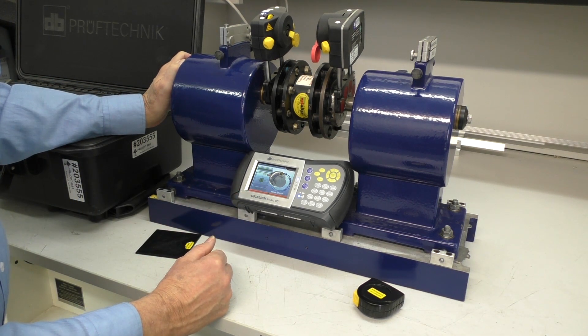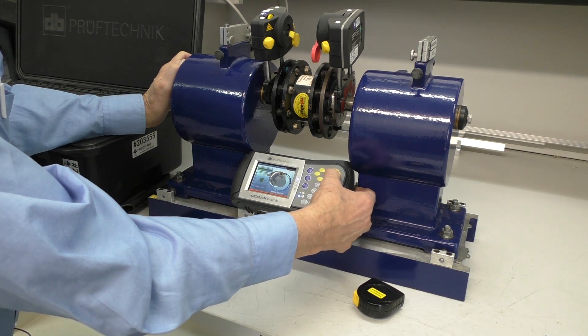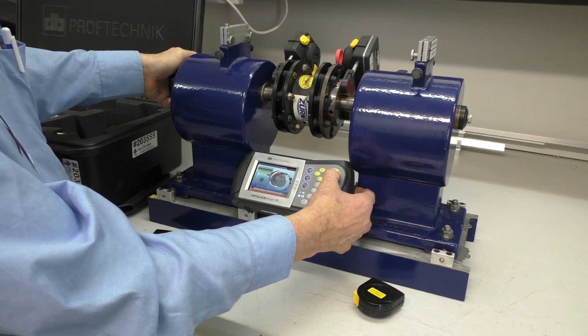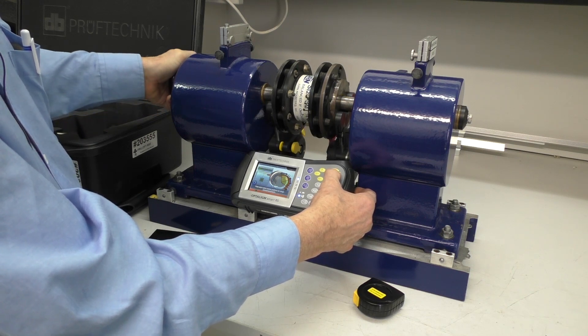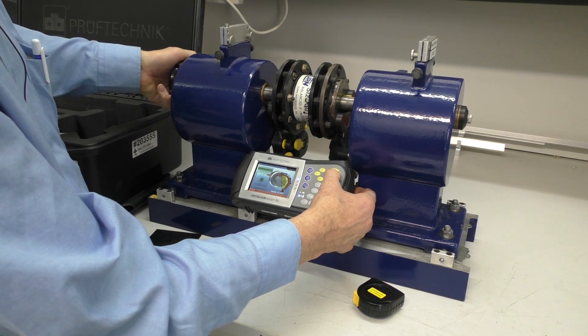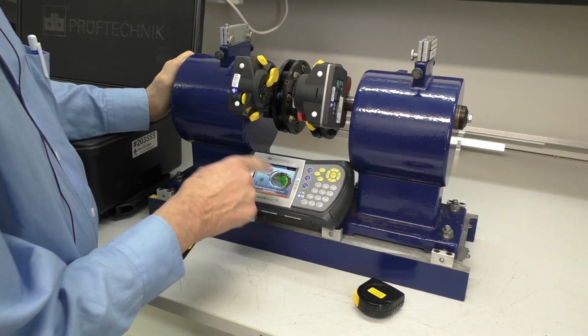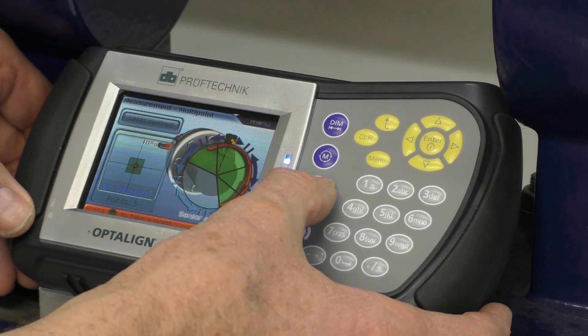There are two types of measurements: we can do three-point measurements or we can do a continuous rotation. The default is three-point measurement. I hit the enter key here and it does a measure. Now I turn it and take another measurement, and I turn it again and take another measurement, and rotate it one last time and take a last measurement. I might just do another — come back up to another point, say over the top here, down this side, measurement there. It's turned green — we've now made our measurement.